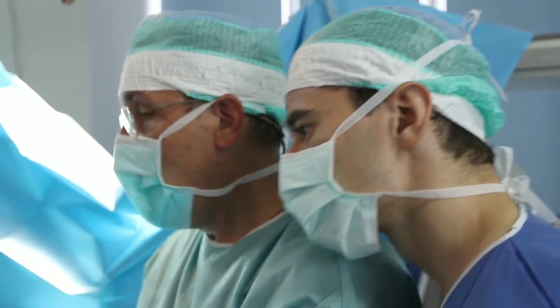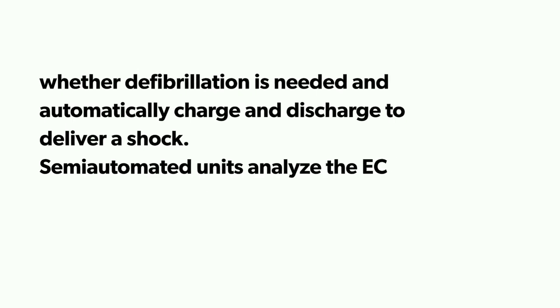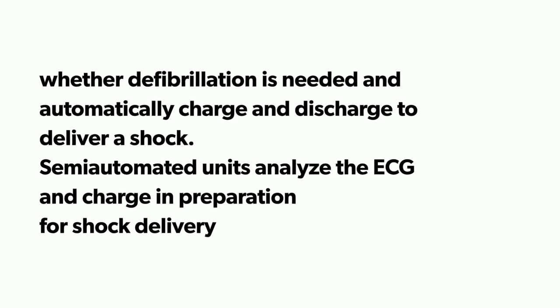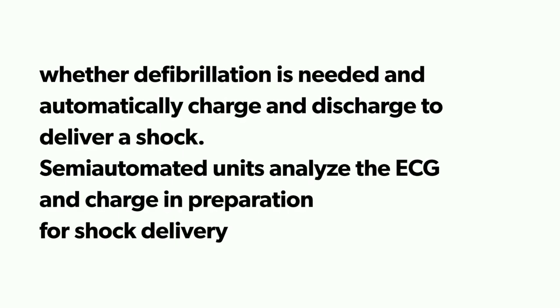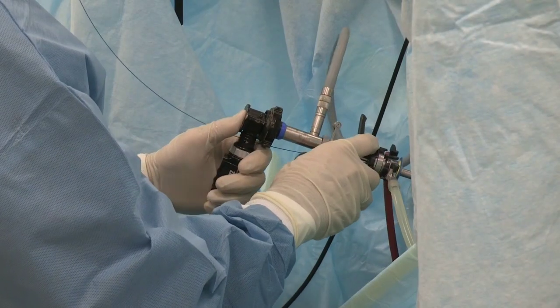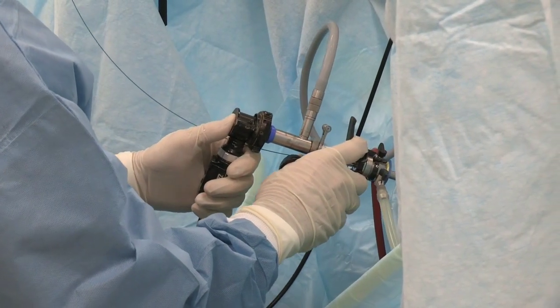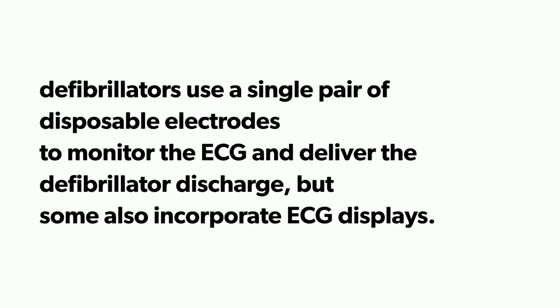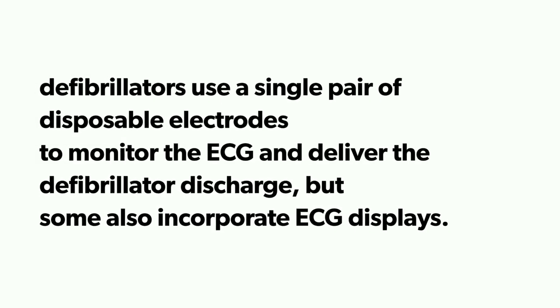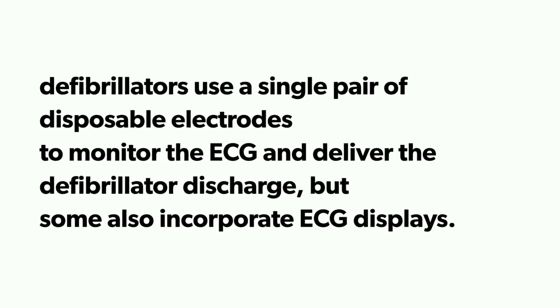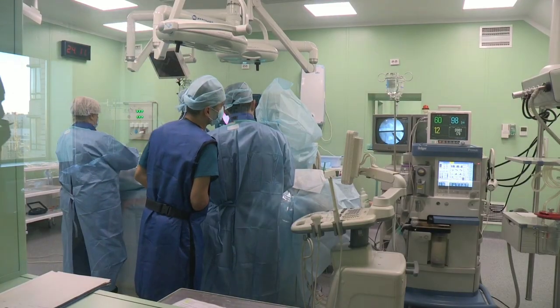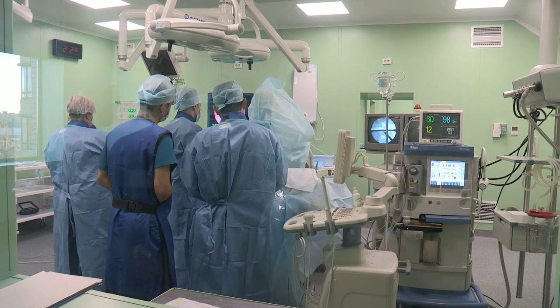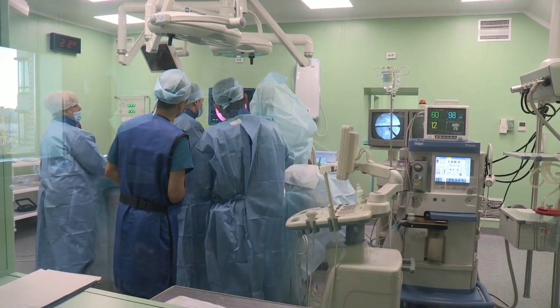AEDs automatically charge and discharge to deliver a shock. Semi-automated units analyze the ECG and charge in preparation for shock delivery, but the operator must activate it. AEDs typically include a memory module or PC data card, a display for status messages, and display of the ECG waveform, which can also prompt the user to initiate a shock.